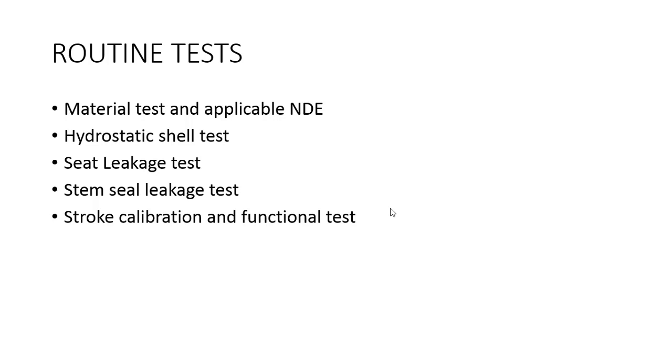Next is the hydrostatic shell test. This test is a must for all pressure containing components. It is used to prove the integrity of the component. A fully assembled valve or only the valve body can be hydro-tested. Normally the valve is unpainted at the time of testing. Do make sure that the valve is completely dry after the testing.